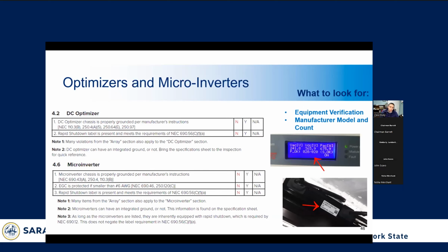All right, so now we're going to jump into DC optimizers and microinverters. A DC optimizer is essentially a DC to DC converter that takes whatever amperage and voltage is produced at the solar panels and converts it to the voltage and amperage required by the string inverter. If you have a DC optimizer, you're going to have a string inverter with the system. A string inverter basically takes the DC voltage from all the panels and converts it to AC power all at one location.